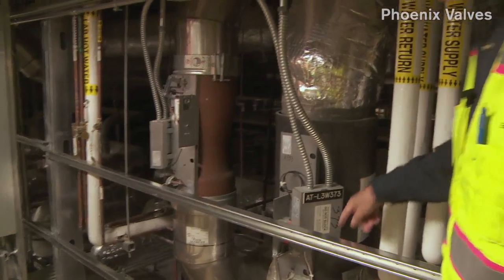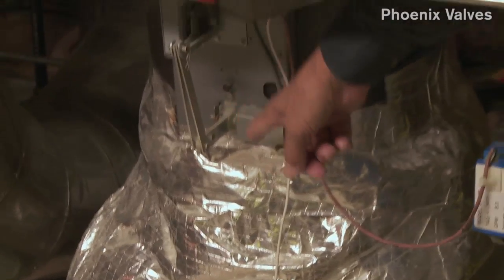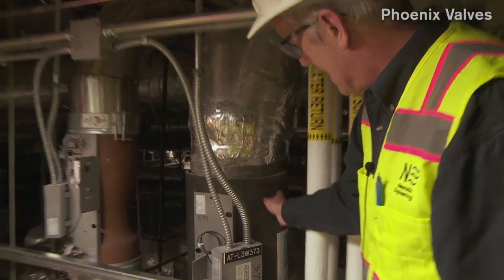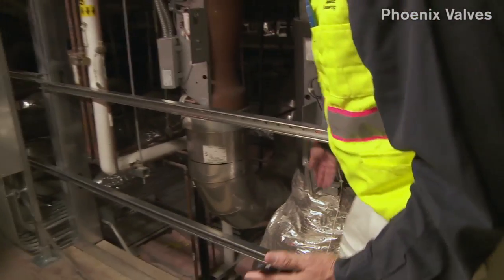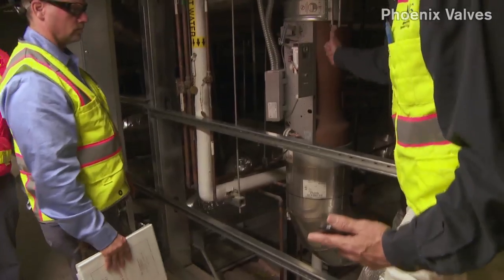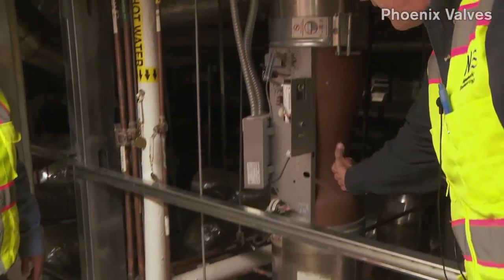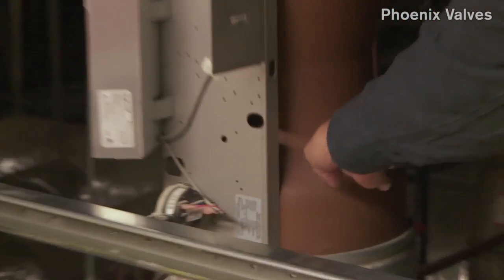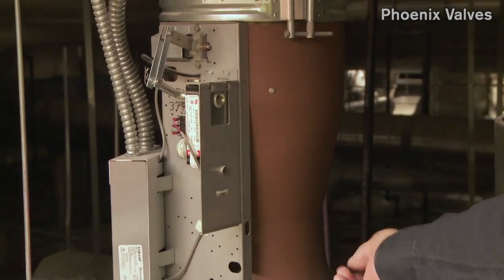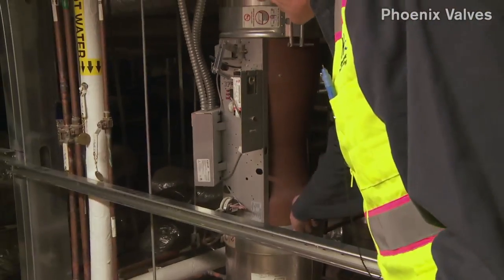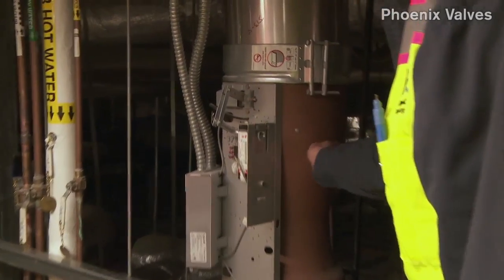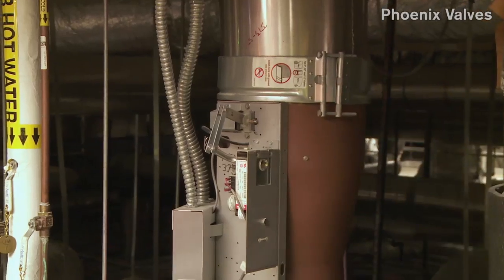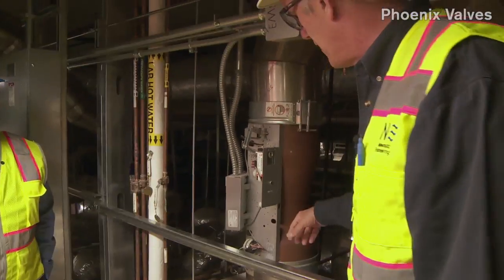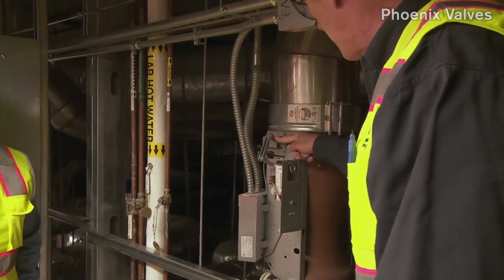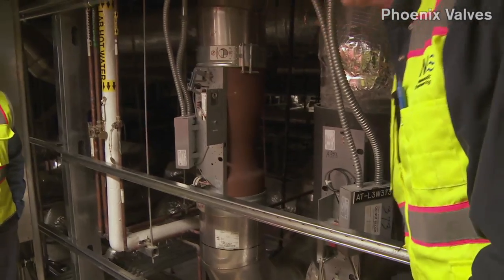Because this is a supply valve, air is actually coming, air enters the valve from this side, and as it leaves the valve, that's where your control arm penetrates the valve body. Then it goes down and into the vivarium. The exhaust, you'll notice your potentiometer is up at the top because air is flowing this way. Air enters at the opposite end of the control arm, goes through the valve. You notice it's got kind of a venturi waist coming in and a conical discharge coming out. That's mainly for acoustics, but air should come into the end where it venturis in quickly and then leaves the part where it conically discharges slowly. So the air doesn't separate as it's flowing through the valve. So you know air is flowing this way because the control arm's at this end. You know air is flowing that way because the control arm's at that end.